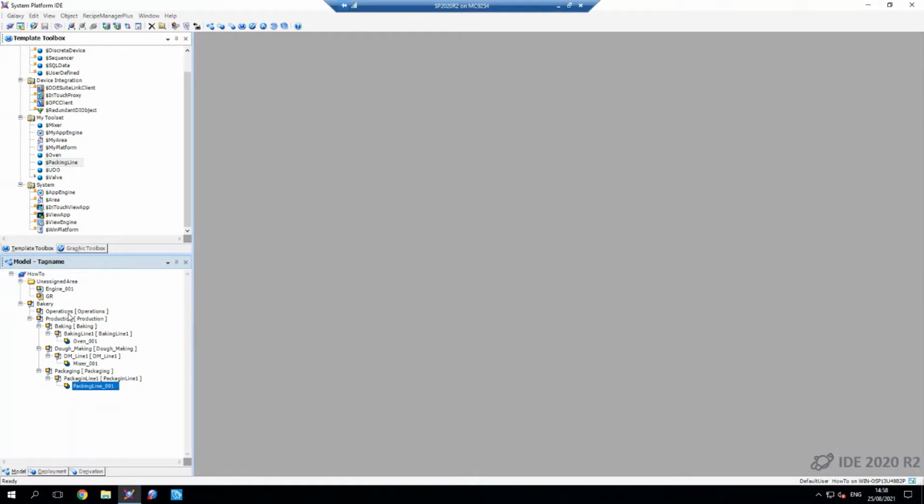So you can see how quickly we've already started to create a hierarchy, a hierarchical view based on those concepts that we went over before. So down from site to plant areas, down to the subdivision areas, down to lines, and then down to the actual pieces of equipment and the actual devices that we're talking to. And that's how easy it is to sort of get started and really start having a hierarchy that makes a difference. So this will serve you in good stead for when you're creating things like OMI applications that leverage this model view and use it to create navigation and associations and drive context. It's all part of a very important foundation.